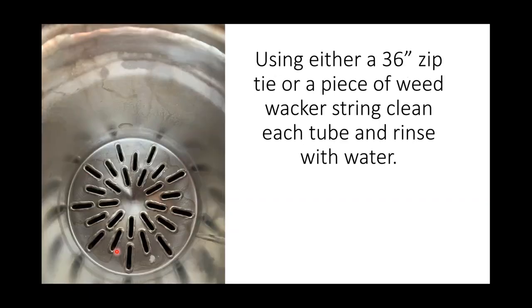So next, here goes a nice clean heat exchanger. This unit has not really been fired much, but we want to clean each one of these tubes. A 36-inch zip tie works real well. Piece of weed whacker string. Run it down through each tube. Rinse it with water. This is going to be a real nice kind of small bucket area, so you don't got to worry about splashing water everywhere. You can get your hose in there and really rinse it out. We want to make sure that all those tubes are clean.